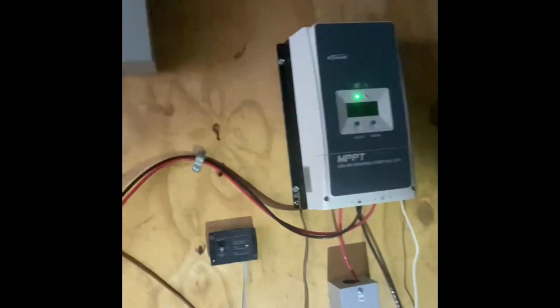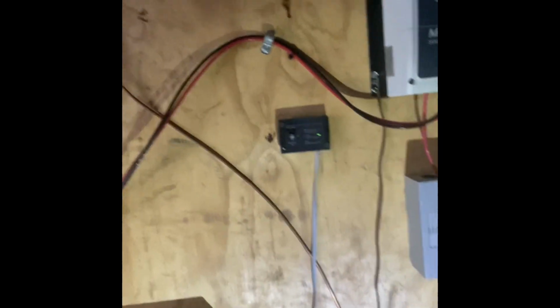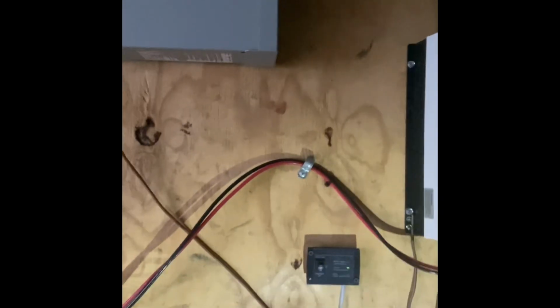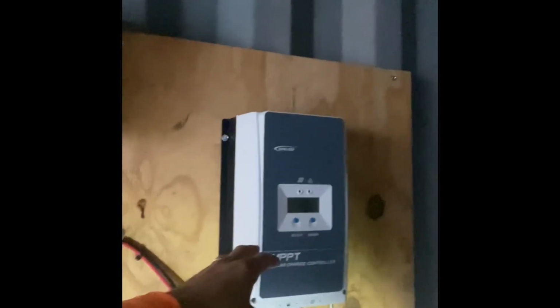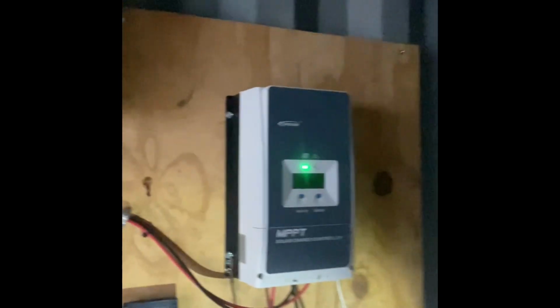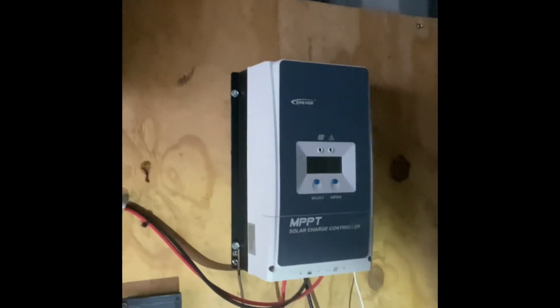And the reason for that is you can isolate each component of your system. You have solar panels, charge controller, batteries, and an inverter. You want to be able to isolate those at any given time for service, maintenance, repair, etc. Or if you have some type of event, overheating, etc., you want to be able to service that and keep your units protected. Otherwise, if you had no way of shutting off your incoming power to your charge controller, you can have a lot of damage to the charge controller. It'd be nearly impossible to repair or operate on if you had a steady supply of current being delivered to it. So let's move on.